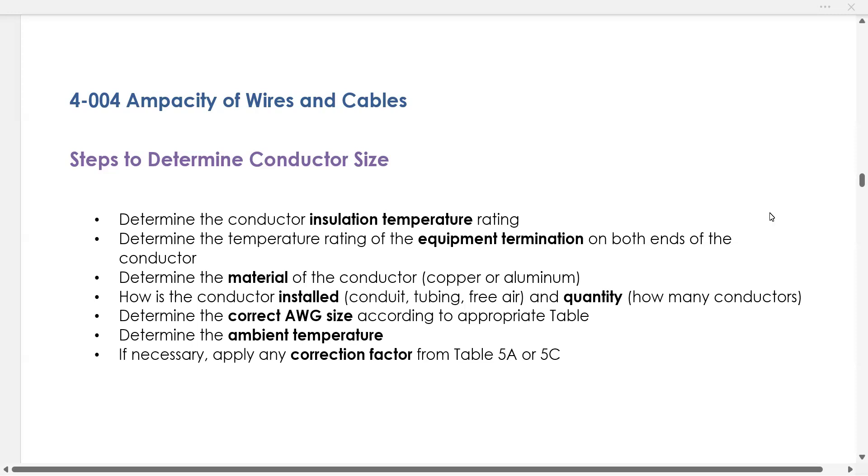So first, you're going to determine the insulation temperature rating. So you will know what type of insulation you need to use for the job, and there is a certain temperature that is associated with that rating. Then you're going to determine the temperature rating of the equipment termination, the terminating point on the equipment at both ends of that conductor. Then you're going to determine which material of the conductor you have, and typically you will know whether you're working with copper or whether you're working with aluminum.